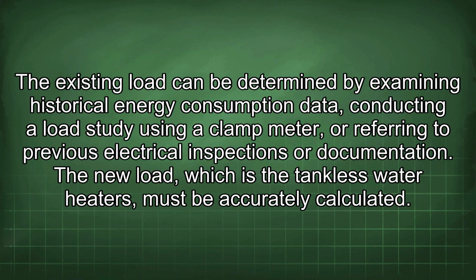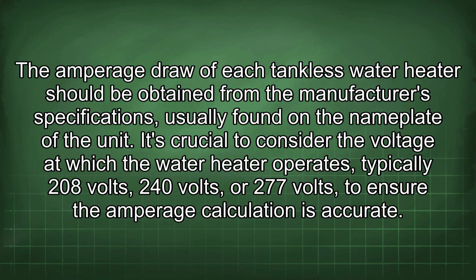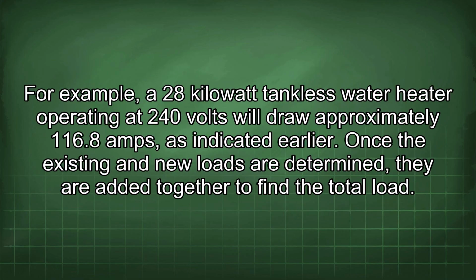The existing load can be determined by examining historical energy consumption data, conducting a load study using a clamp meter, or referring to previous electrical inspections or documentation. The new load, which is the tankless water heaters, must be accurately calculated. The amperage draw of each tankless water heater should be obtained from the manufacturer's specifications, usually found on the nameplate of the unit. It's crucial to consider the voltage at which the water heater operates, typically 208 volts, 240 volts, or 277 volts, to ensure the amperage calculation is accurate. For example, a 28 kilowatt tankless water heater operating at 240 volts will draw approximately 116.8 amps, as indicated earlier.